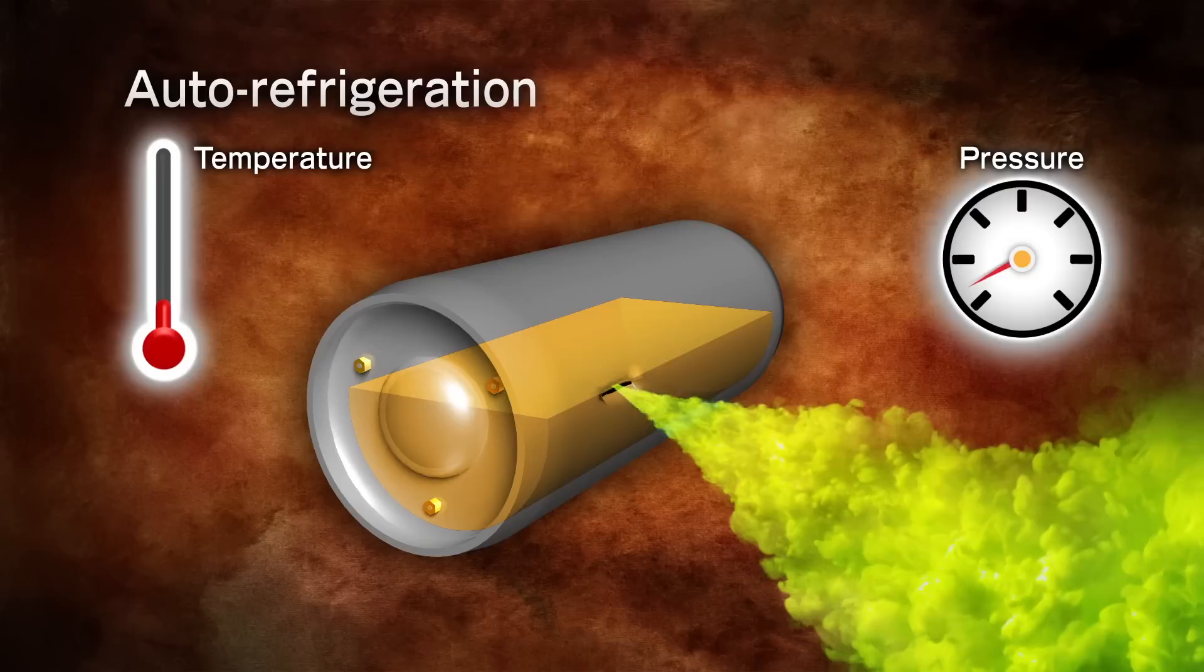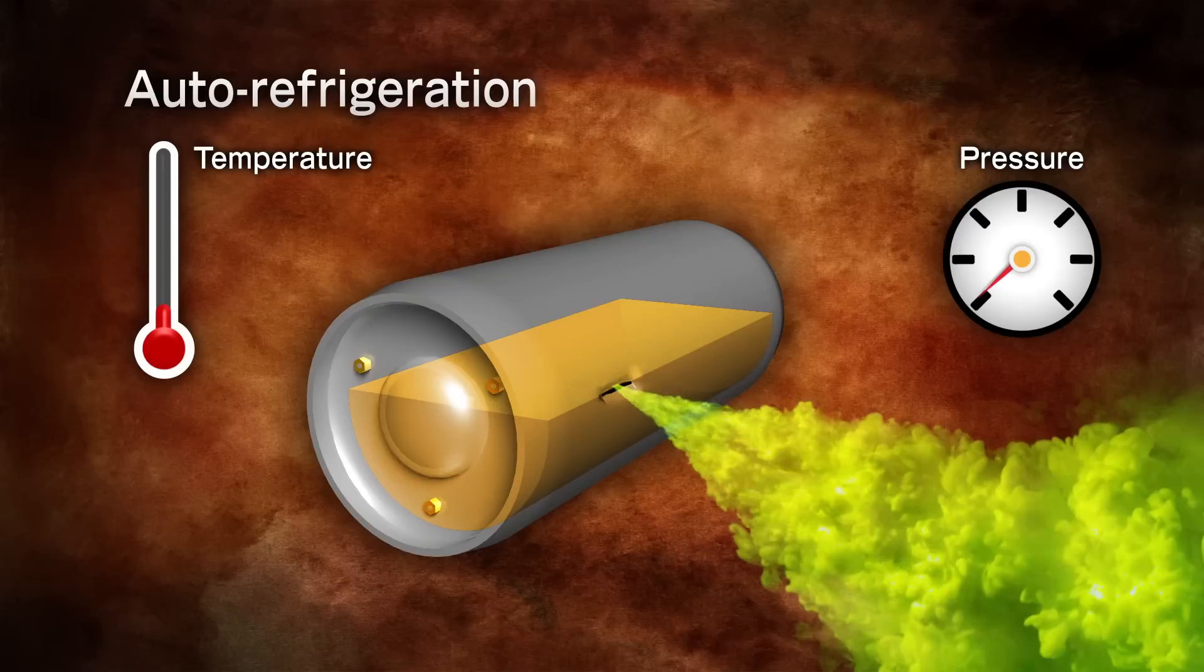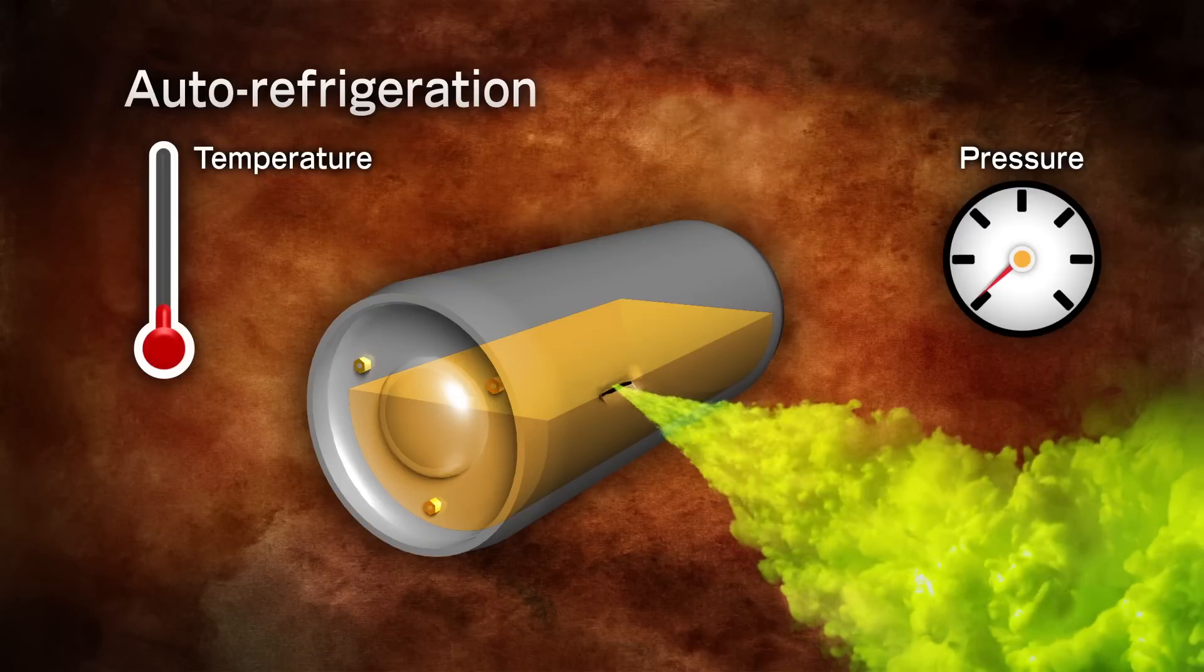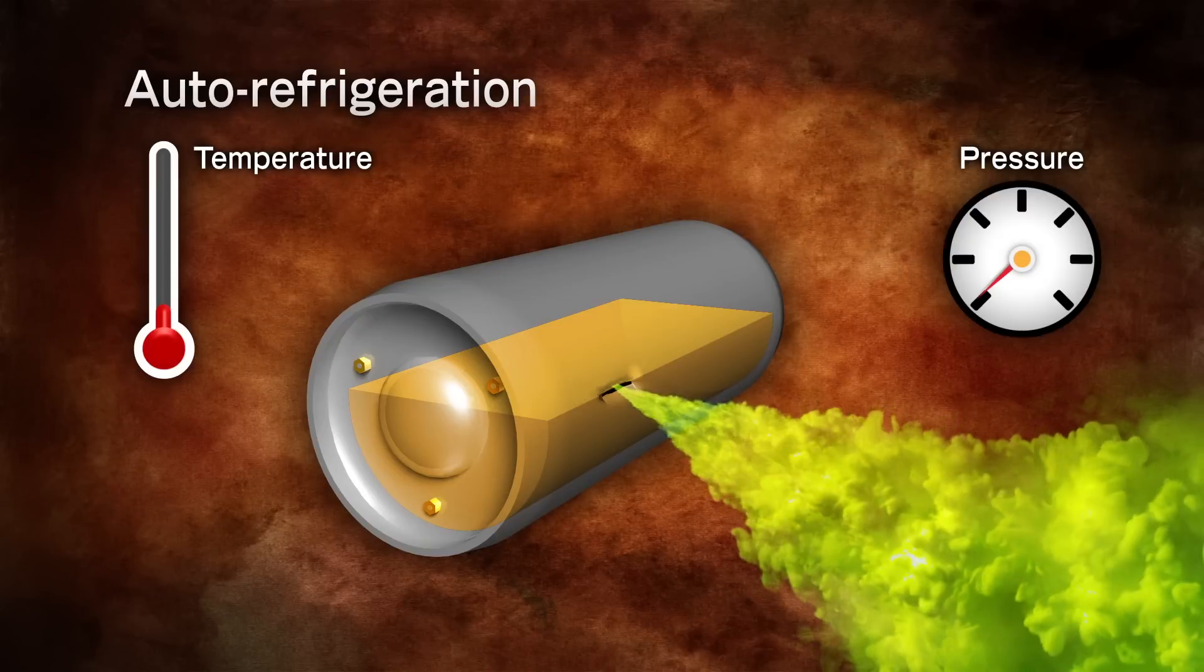auto-refrigeration takes place. Auto-refrigeration is the result of chlorine quickly escaping from the container, which causes the chlorine to cool down below its boiling point at the new lower pressure condition.